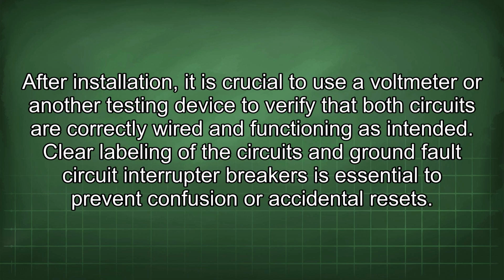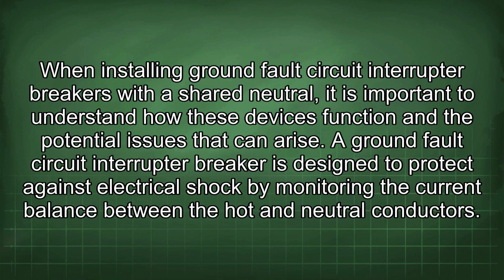After installation, it is crucial to use a voltmeter or another testing device to verify that both circuits are correctly wired and functioning as intended. Clear labeling of the circuits and ground fault circuit interrupter breakers is essential to prevent confusion or accidental resets. When installing ground fault circuit interrupter breakers with a shared neutral, it is important to understand how these devices function and the potential issues that can arise.